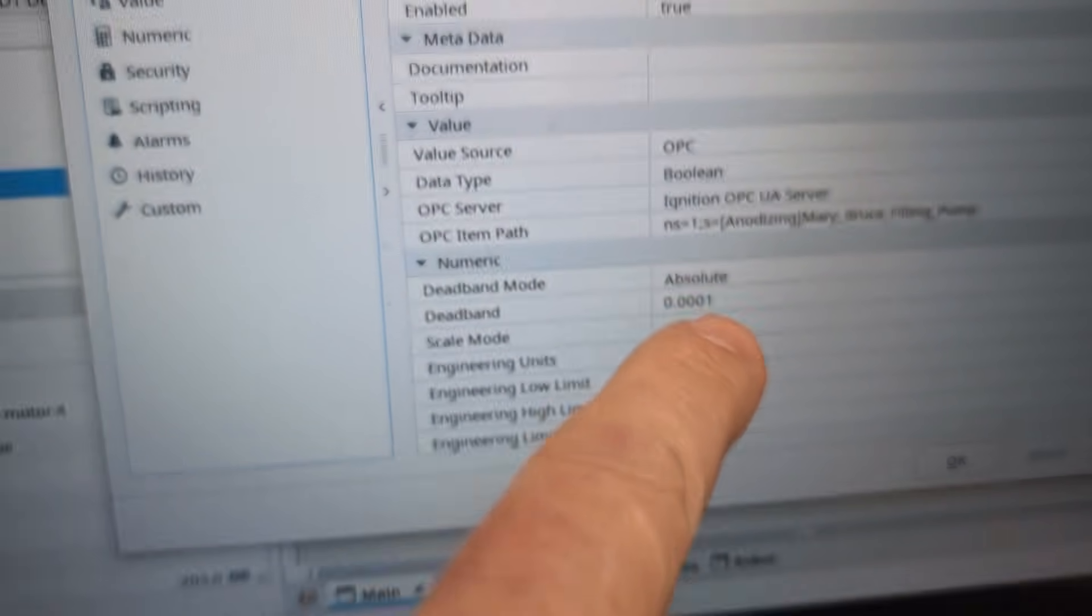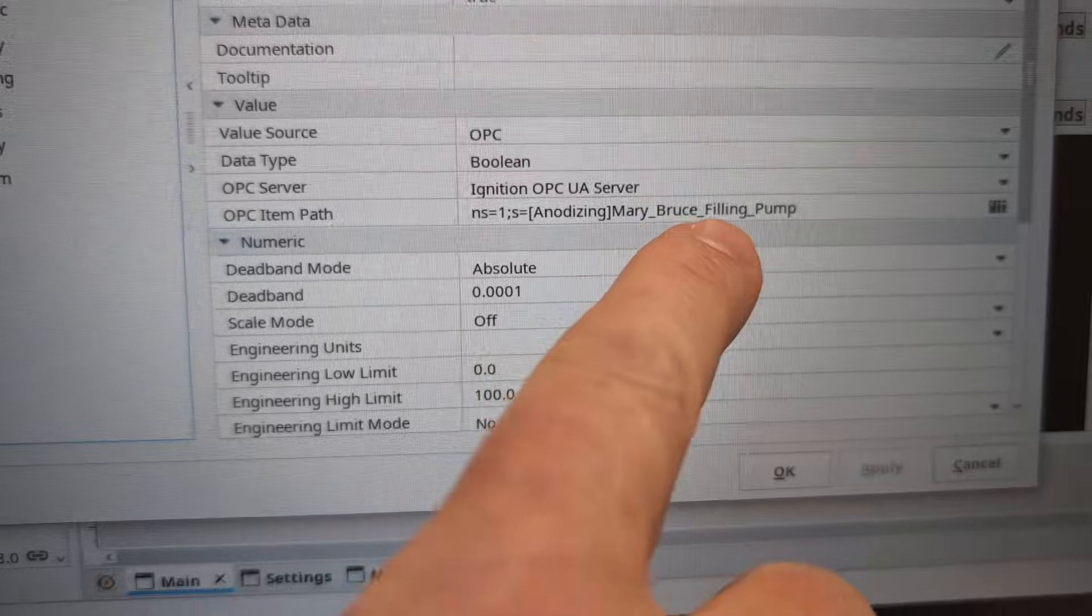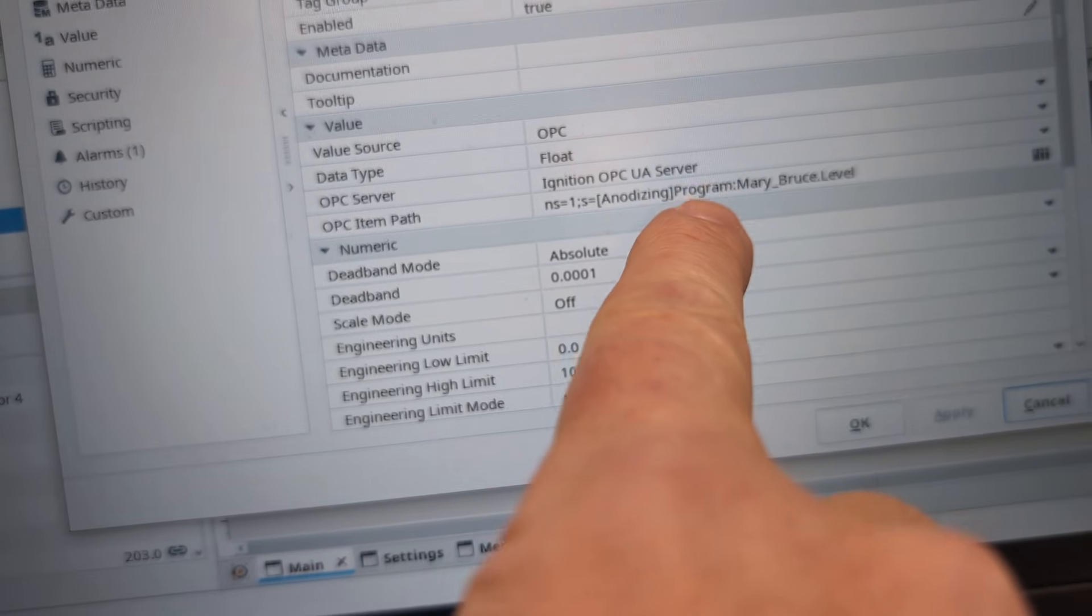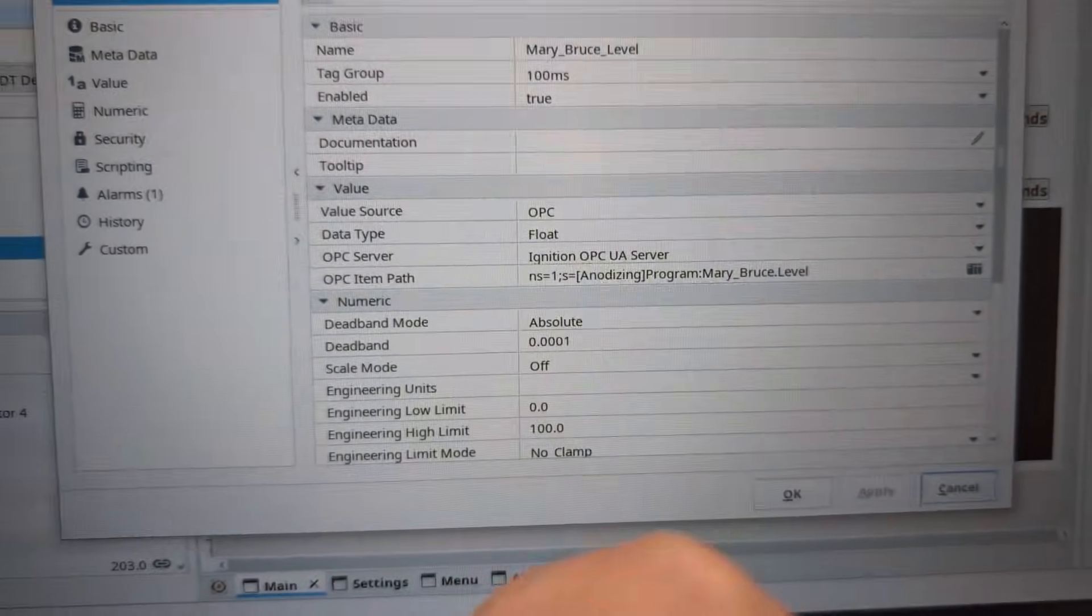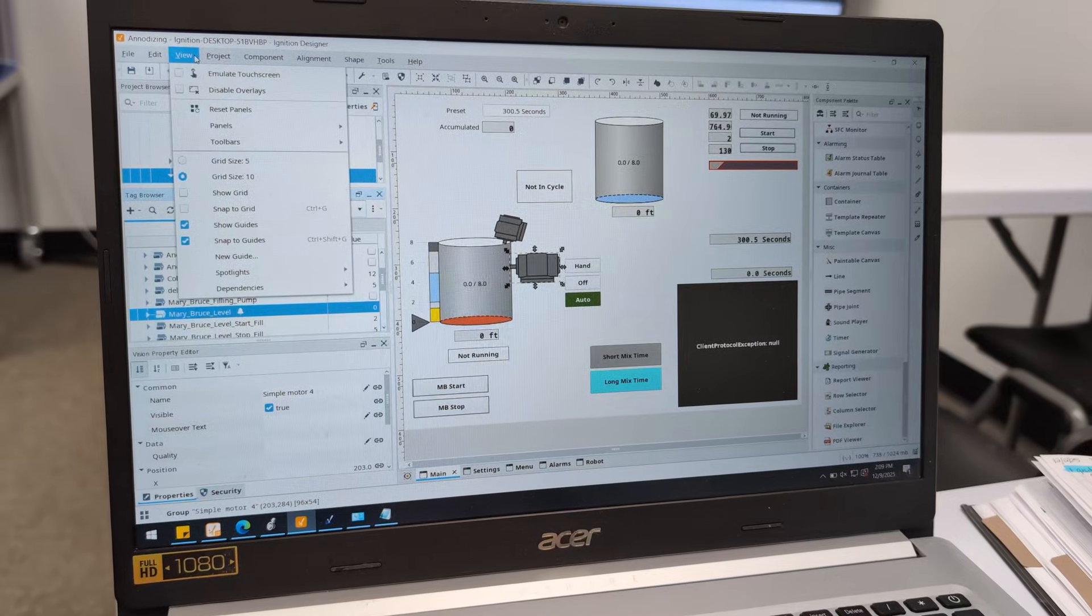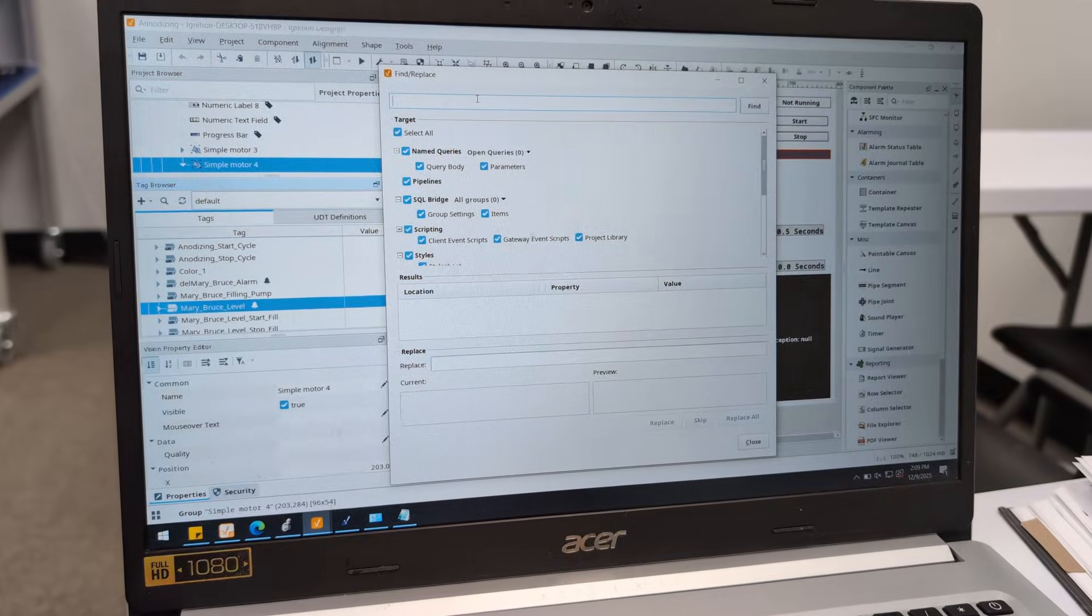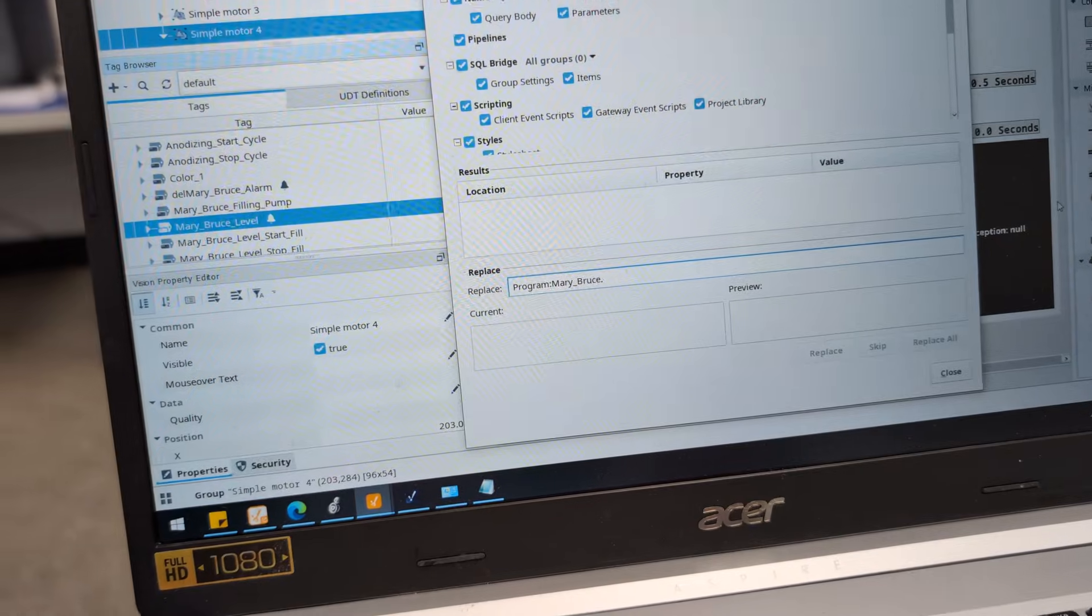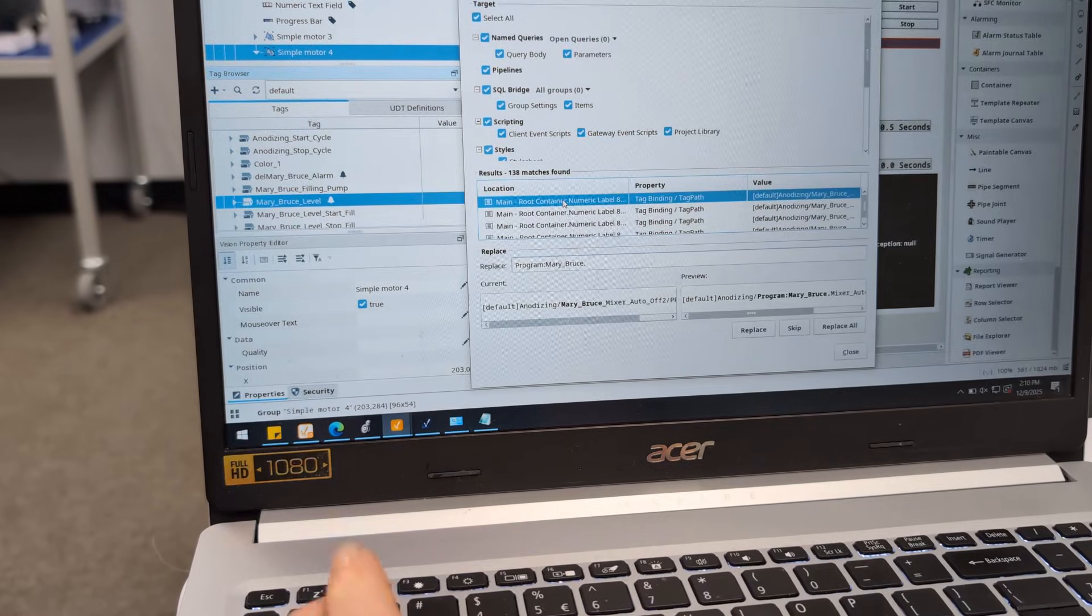Now the next thing is we got to modify all the tag names because yeah, they were MaryBruce_FillingPump. This needs to be something such as what we did on this level which is Program:MaryBruce.Level. Now we could do these one at a time but we go big or go home, so we're going to use the nice Find and Replace feature. All the pressure's on - see if Mary Bruce can do it with the video going. We're going to take and replace Mary_Bruce_ with Program:MaryBruce dot. And we're going to Find Replace All.